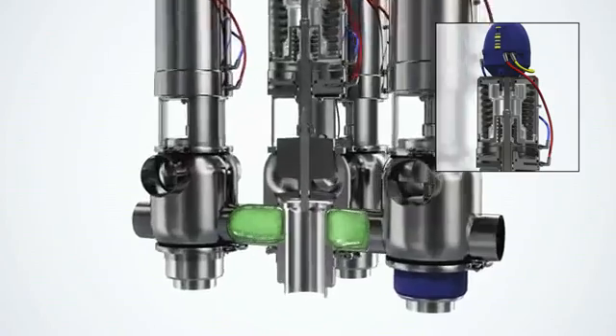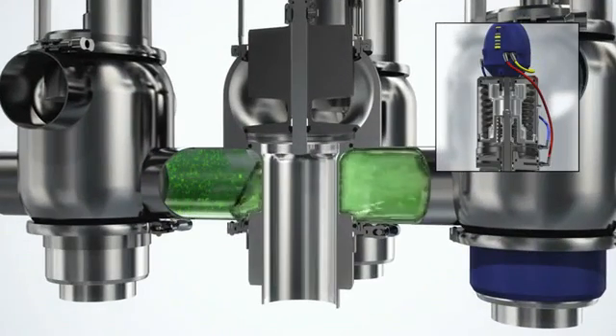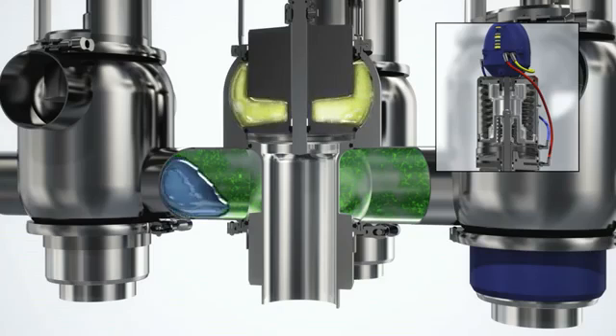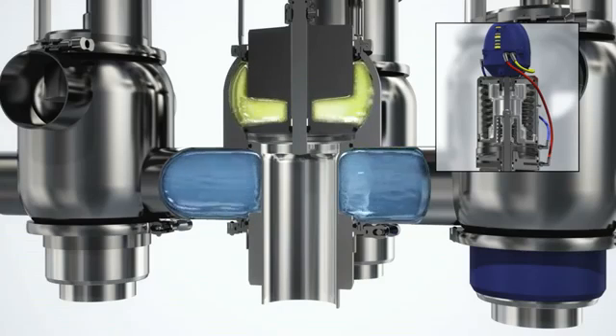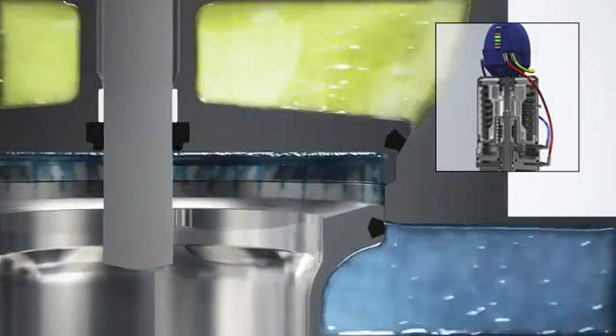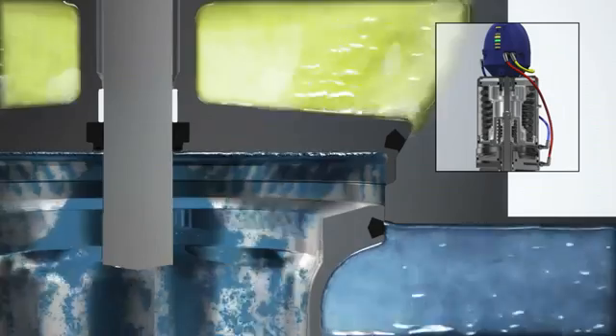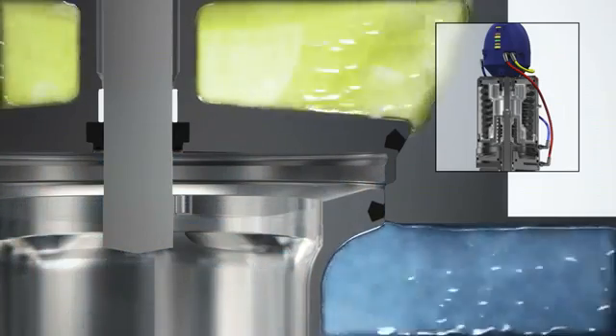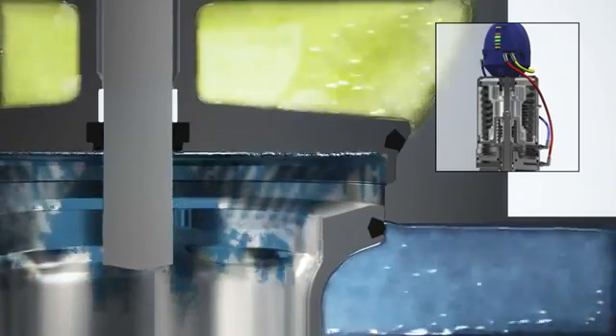Alfa Laval unique mix proof LP valves enable the simultaneous flow of two different products or fluids through the same valve without any risk of cross contamination. Like the seat lift operation, the fast acting seat push function is controlled within the actuator by a defined metal to metal opening, which provides a throttling edge.